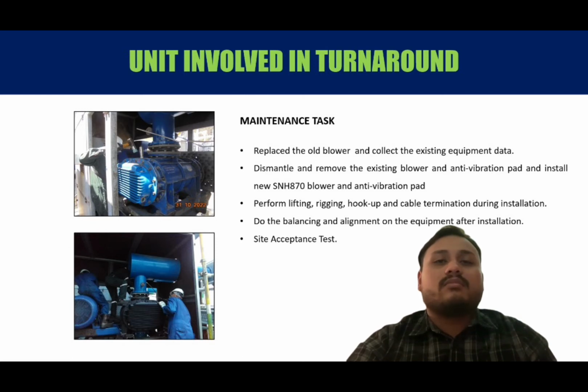vibration below 8 mm per second, taken using a vibration data logger, with no abnormalities in the spectrum and the time waveform such as defect frequency, and the bearing temperature must be below 80 degrees Celsius, measured at the casing surface. The contractor should develop a procedure for FAT, factory acceptance test, and submit the procedure to the owner for review and approval.